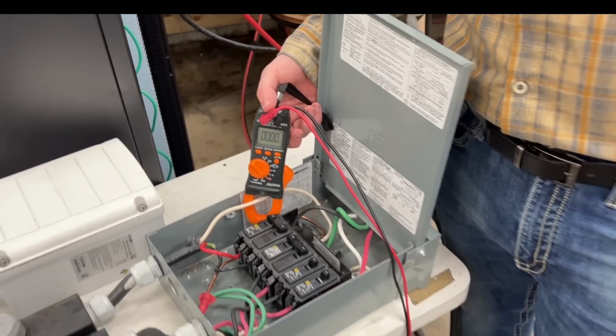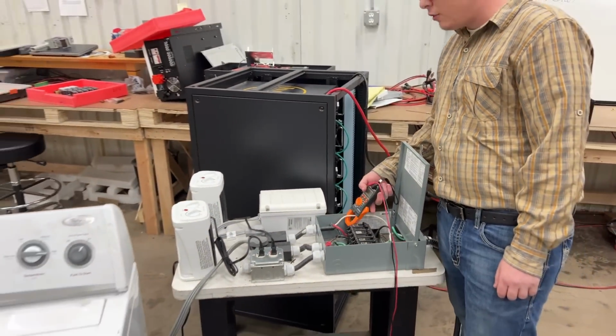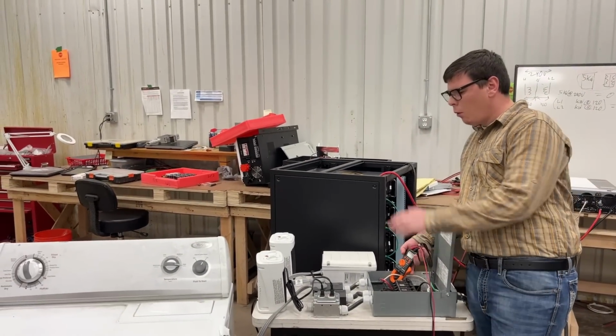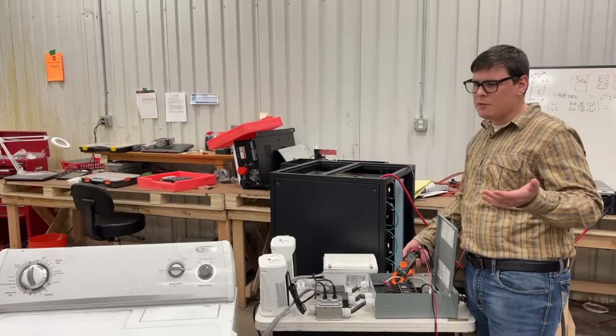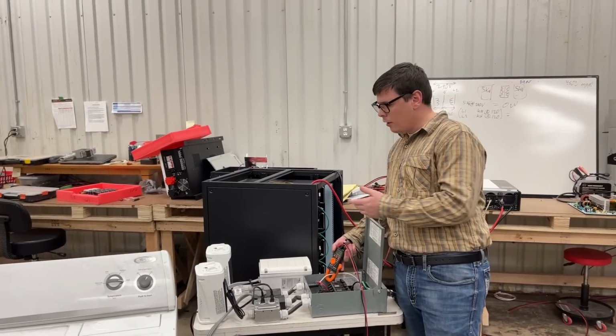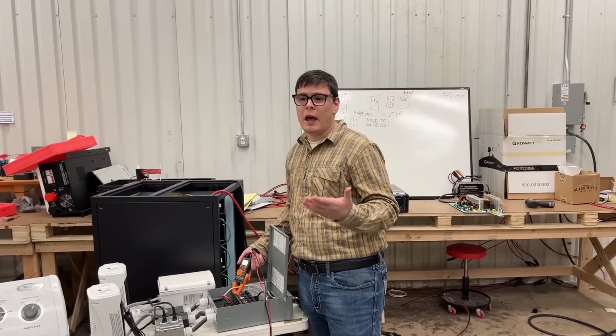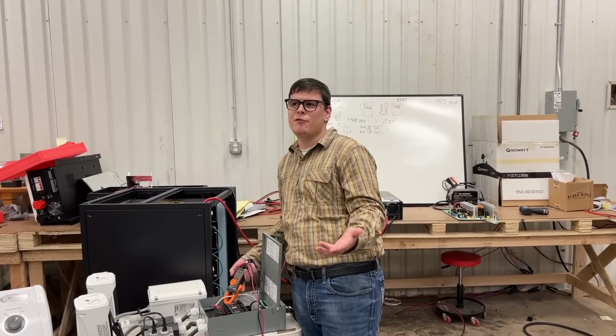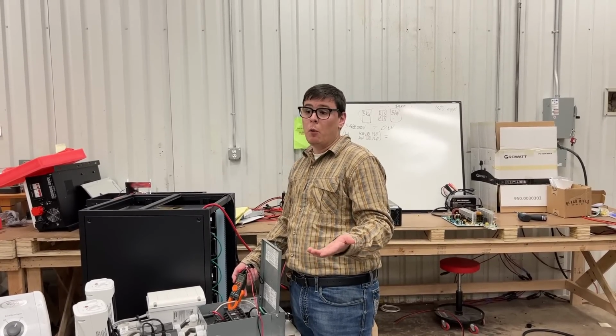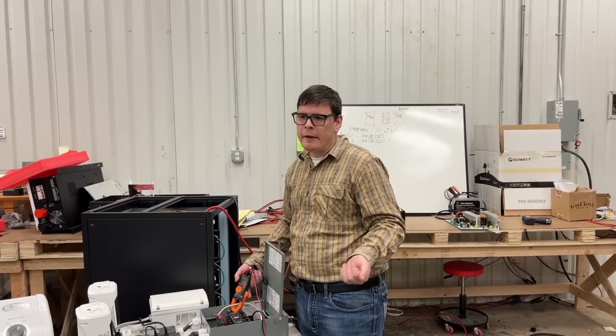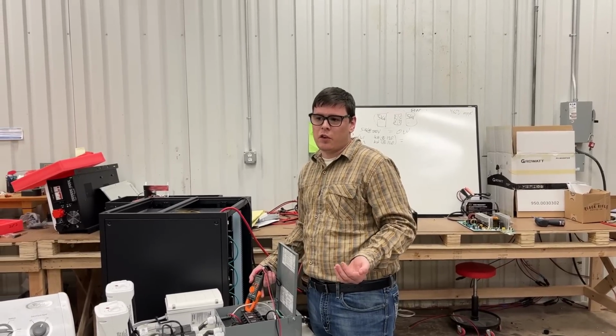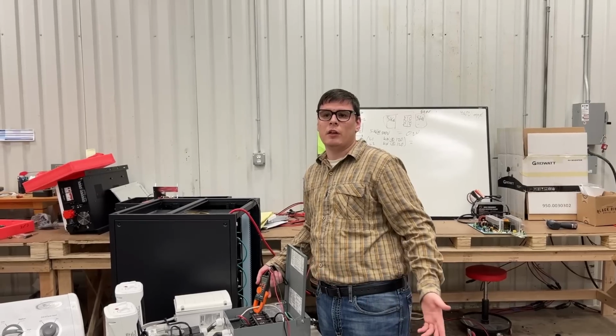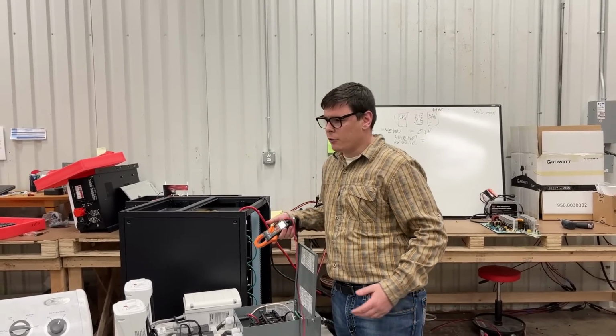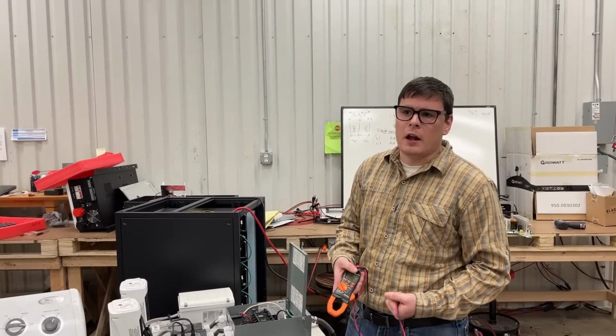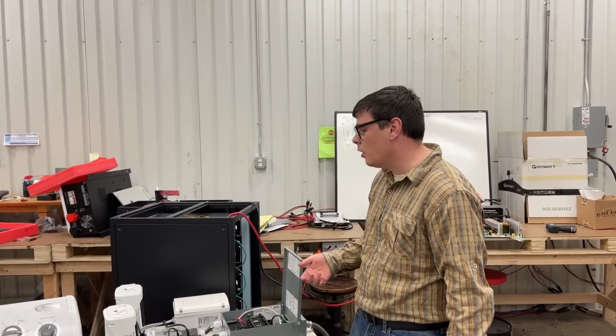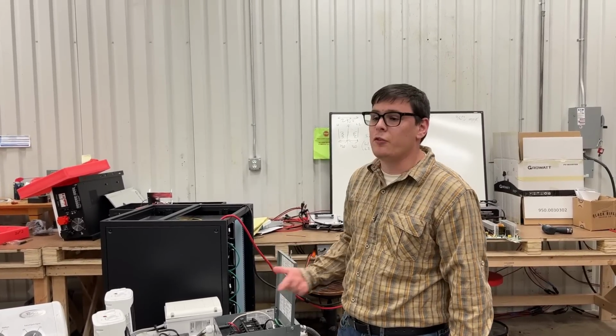So that's kind of a good illustration as to how all this works. It's not even pulling the total load of these. It's the probability of how far imbalanced. If you have 5 total kilowatts of 120s, which again is pushing it, and you say, well, what's the probability of me imbalancing those? I mean, if you're living off grid, you're living intentionally. You've got an idea as to when you're pulling these kind of heavy loads, and you've got a plan based around that.